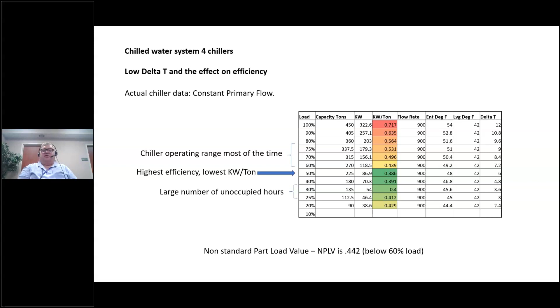Most of the time, it's going to operate at a less efficient point. The unoccupied hours, it's operating down here on the bottom. Now, if you didn't know it, at the low end, some chillers are not as efficient. You want to find the most efficient point for this system to operate and try to channel it into operating at that point. Note the delta T with a constant flow of 6 degrees at the most efficient point of operation. That's the lowest energy point. 70% of the time, though, it is not running in the most efficient range.